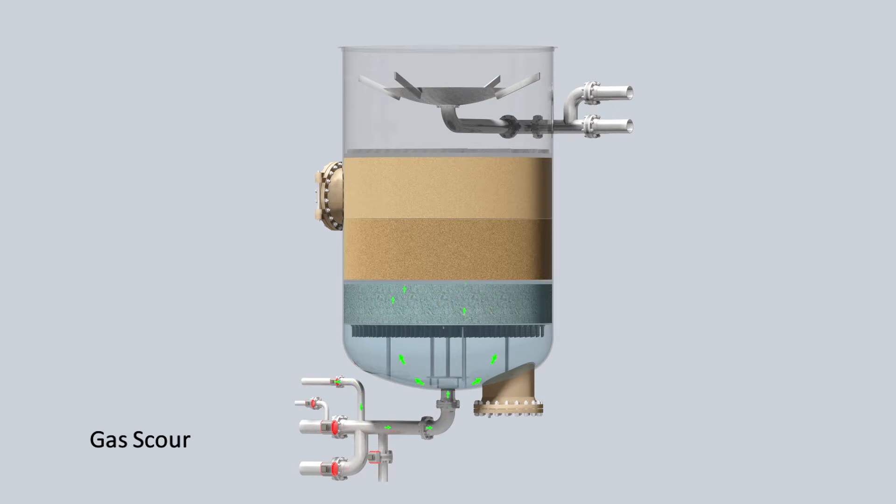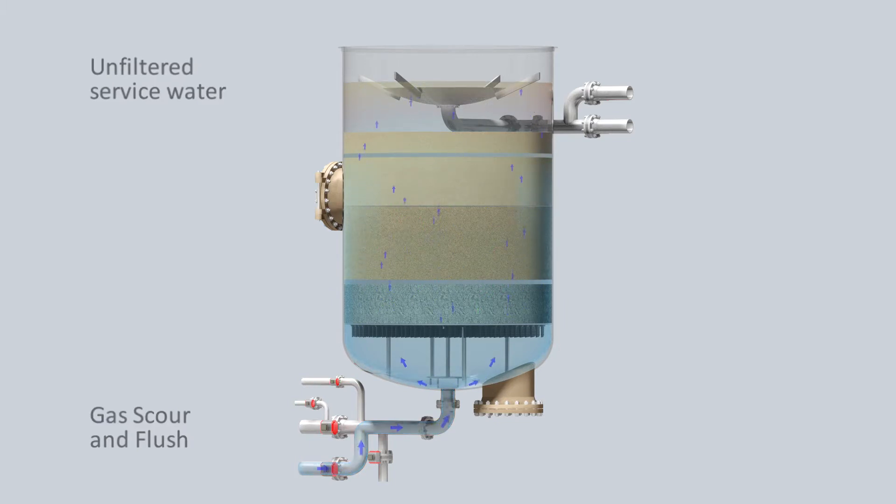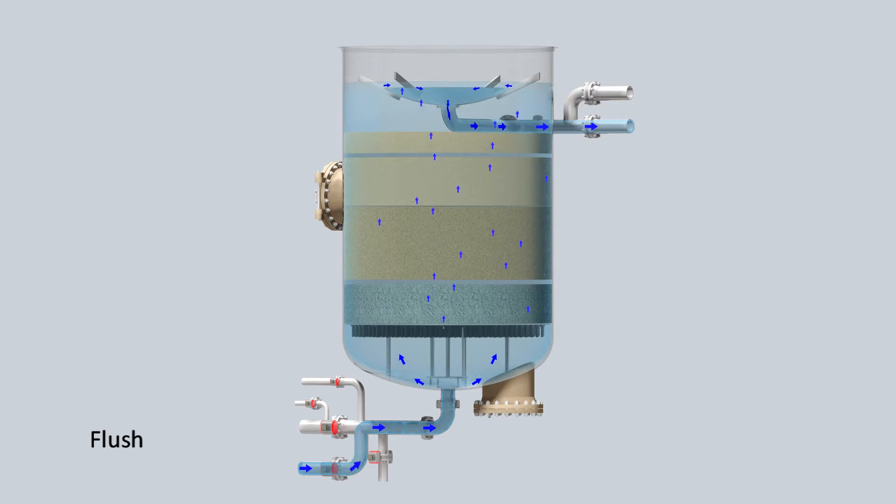The flush flow expands the media letting contaminants pass through the bed and out of the filter as a waste stream to be further treated. Upon completion of the first flush cycle, the filter repeats the same cycle a second time to ensure thorough cleaning of the media.